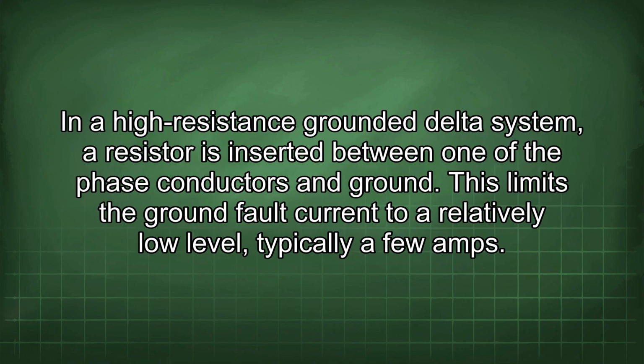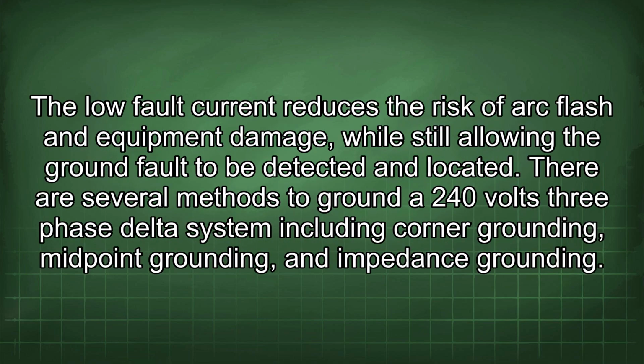In a high-resistance grounded delta system, a resistor is inserted between one of the phase conductors and ground. This limits the ground fault current to a relatively low level, typically a few amps. The low fault current reduces the risk of arc flash and equipment damage, while still allowing the ground fault to be detected and located. There are several methods to ground a 240 volts three-phase delta system, including corner grounding, midpoint grounding, and impedance grounding.